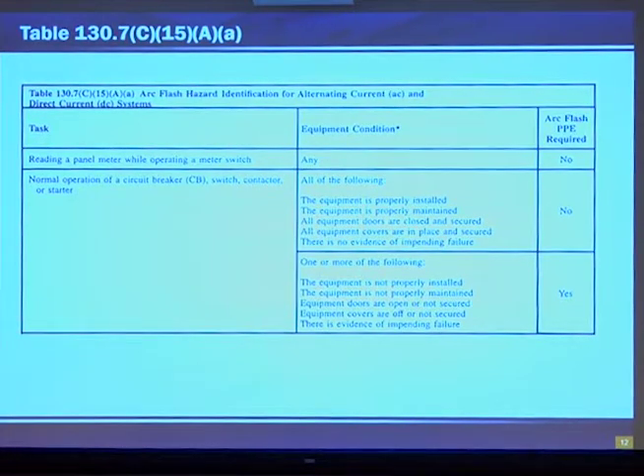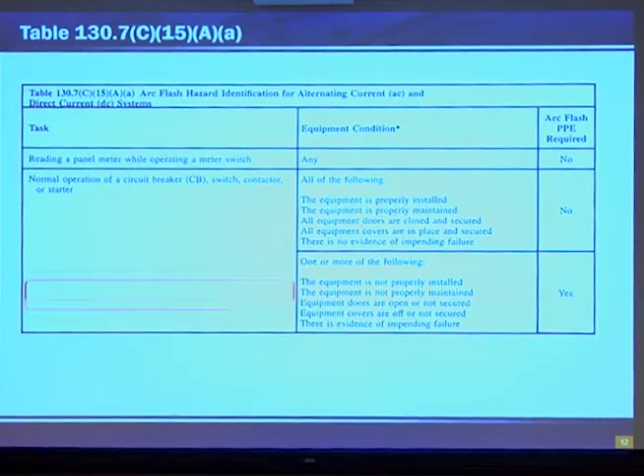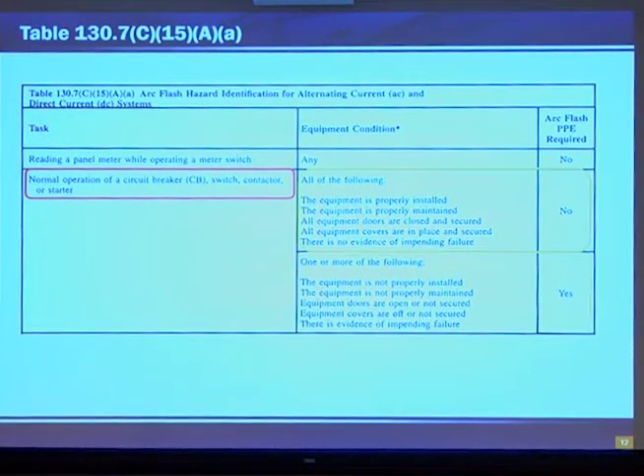So say our preventative maintenance plan calls for us to check the operation of lights on a highway or traffic signal. So we go out there, we have to turn on and off some circuit breakers or flip a hand-off-auto switch. So our task would be the normal operation of a circuit breaker or turning off a switch. Now, if our equipment is properly installed, properly maintained, the doors are closed and secured, the equipment covers are in place, and there's no evidence of impending failure, then our table says no ArcFlash PPE is required. Now remember, we're looking at the 2015 NFPA 70E.